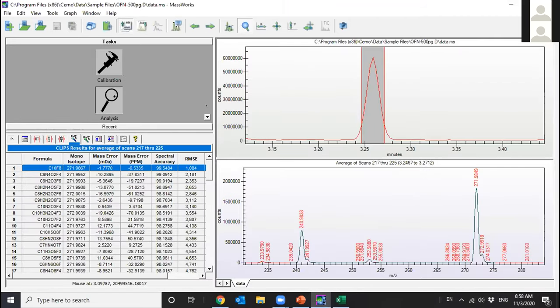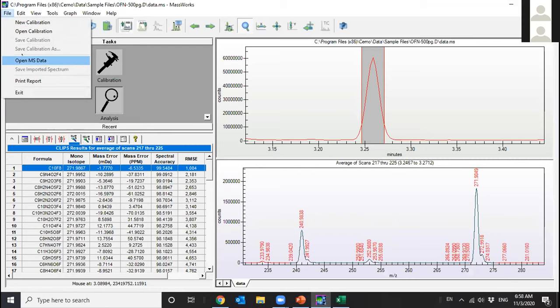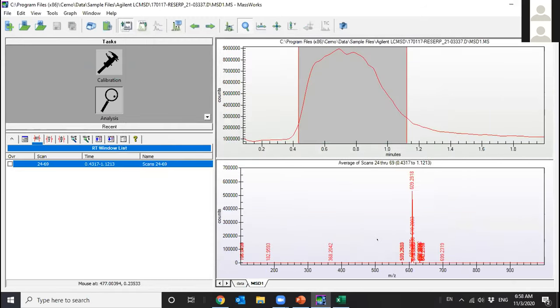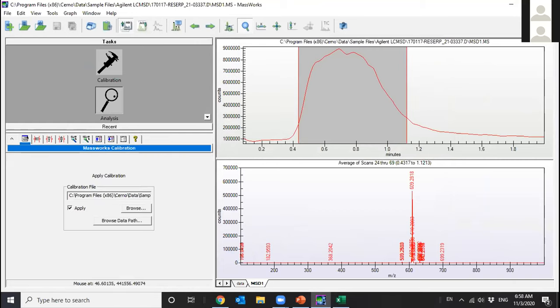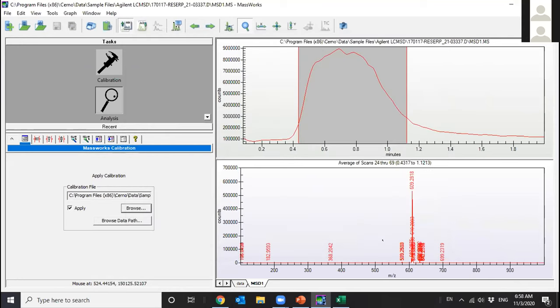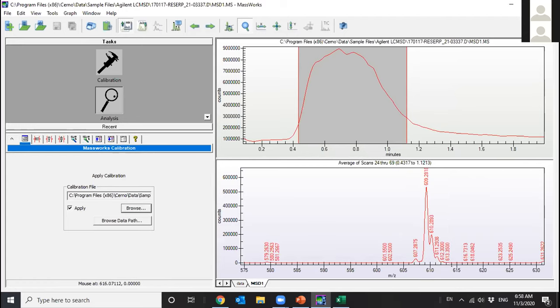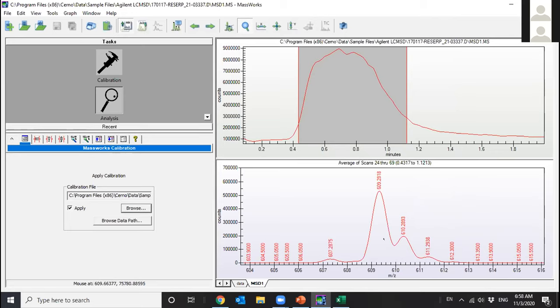You go to analysis, and under analysis, you would go and open a sample run. In this case, it's a reserpine sample run. Go open the .ms file under analysis, and then you go here to apply the calibration, which is what we just created. You go navigate to where the calibration file has been saved. You say open, that's applied. So this is the 609 after averaging the peak, and after calibration.